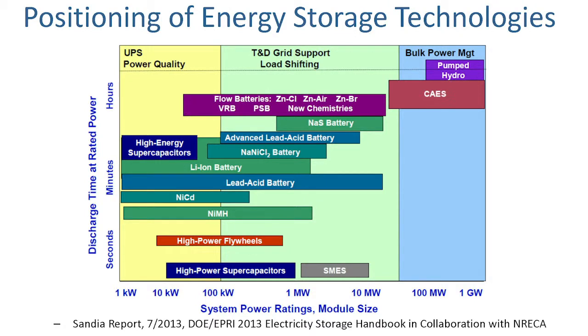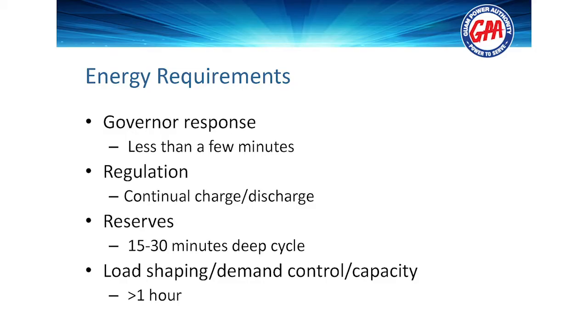This is the position of energy storage technologies. This is what we talked about before about how long the energy needs to be available, 15 minutes, as to what technology is there. You can see if you need to go out for 15, 20 minutes, there's really only batteries, pumped hydro, and some flywheels. 15 minutes for a flywheel is really at the extreme edge of a flywheel. I know that they say you can actually do it, you can parallel the flywheels and get that out there, but it's a huge cost. Flywheels have a lower life cycle cost than batteries, but they have a huge installation cost. Okay, next. Although I got to say that's coming down. In fact, I think one of the companies out of Australia is probably one of the leaders in driving down the cost of flywheel technology these days.